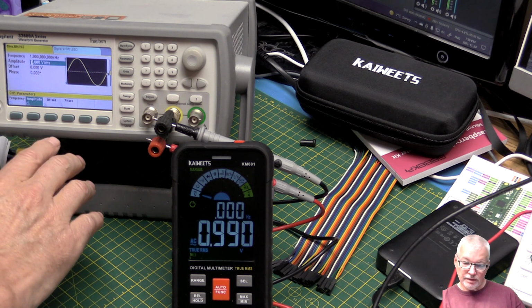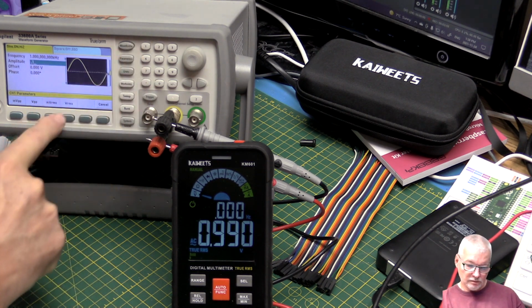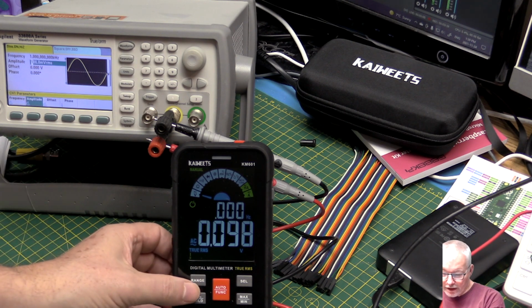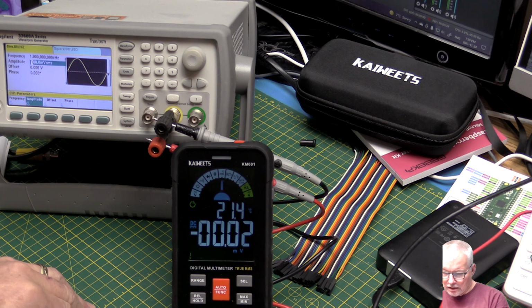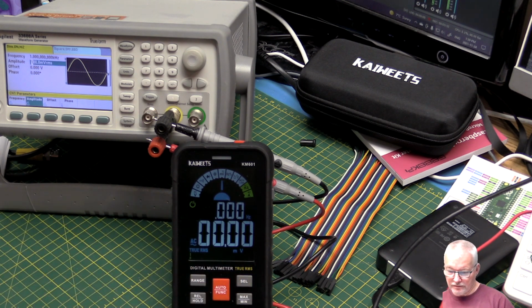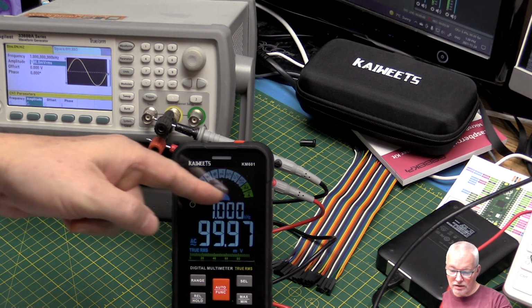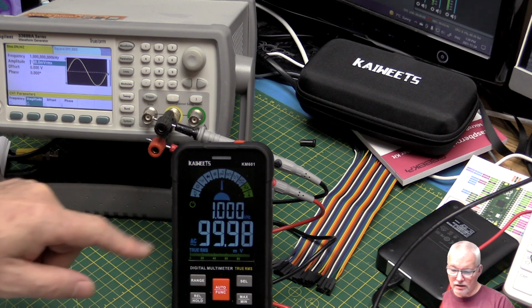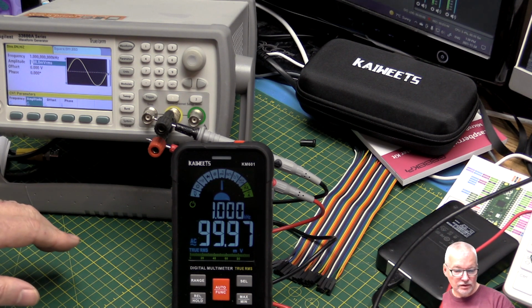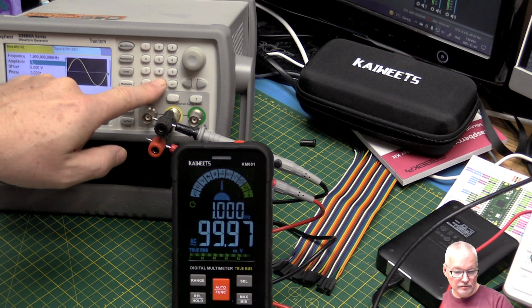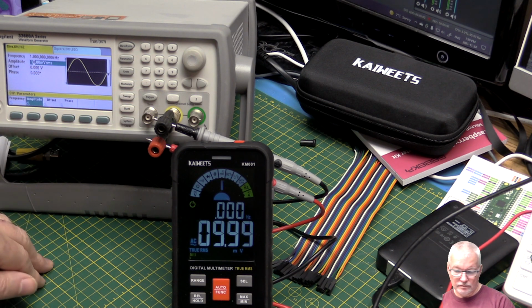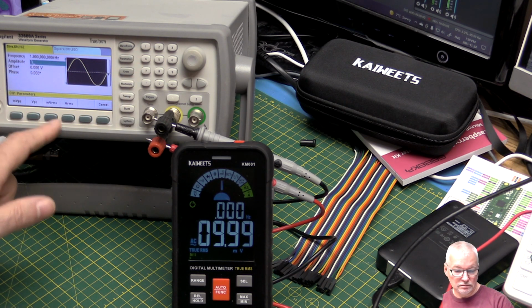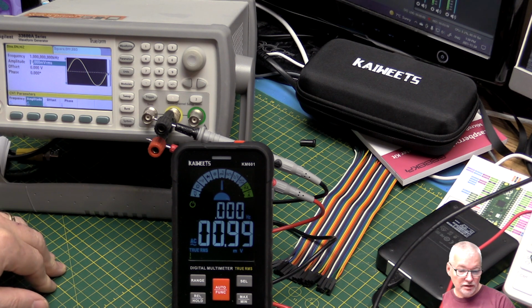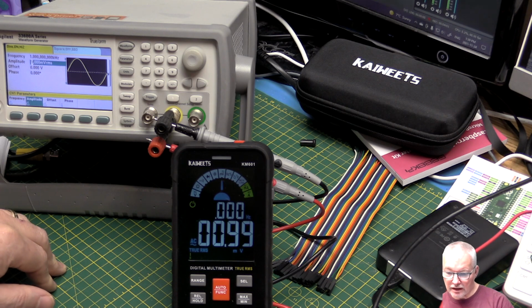So let's go down to 100 millivolts RMS. Let's flip range to the millivolts. Oh, and we have to select AC. There we go. So that's reading pretty accurate for 1 kilohertz. It measures the frequency as well, and the volts is reading accurate. So that's good. Let's go down to 10 millivolts. So that's doing pretty good. 1 millivolt. And it's still doing very good. So I think that's probably good enough for checking the millivolts range.